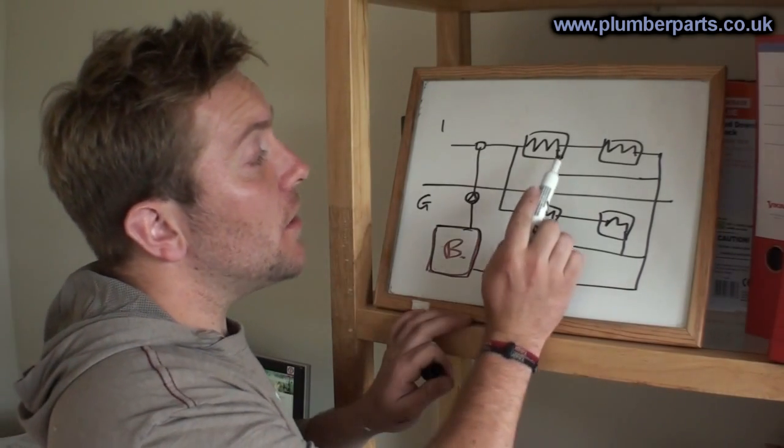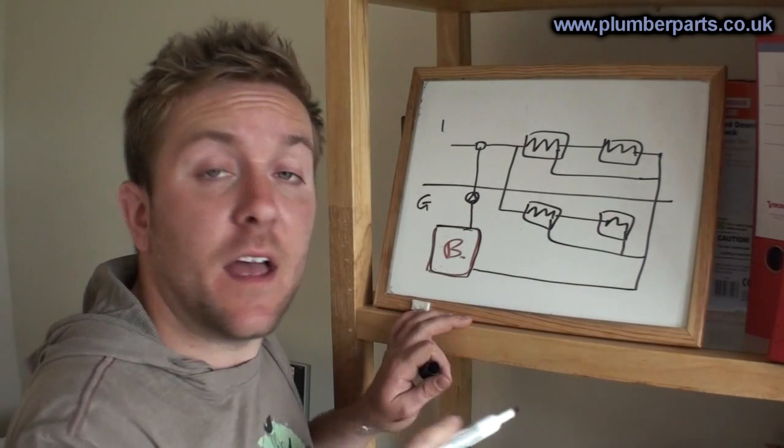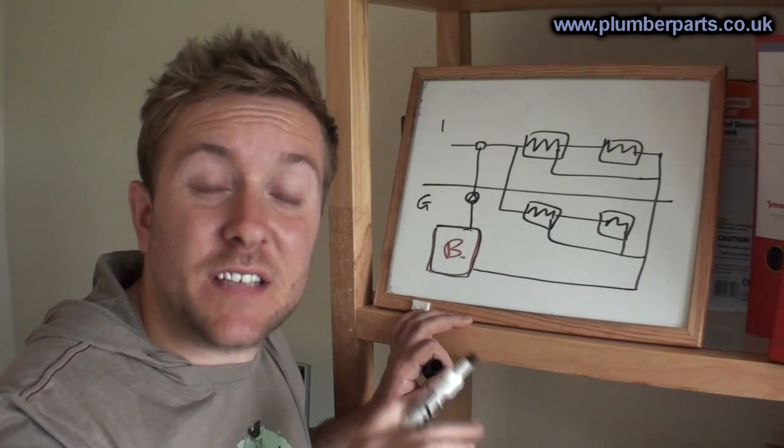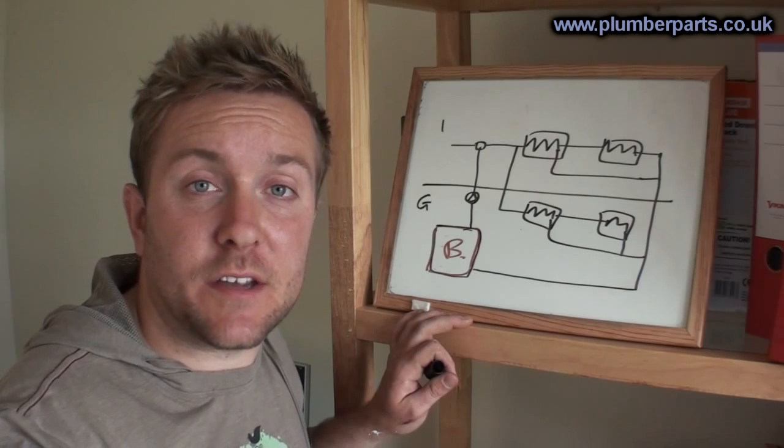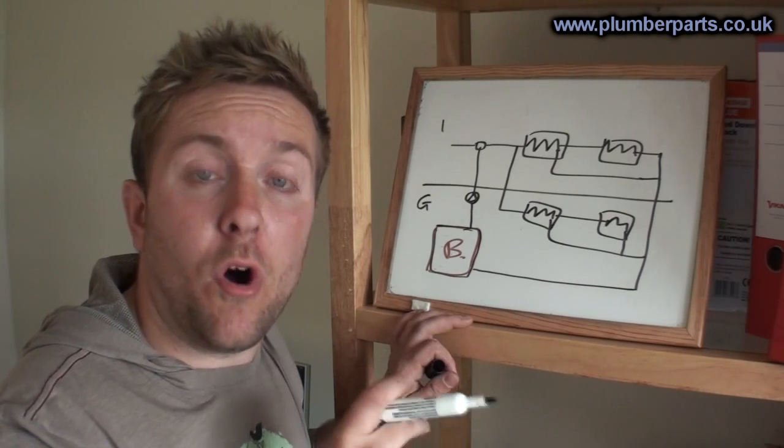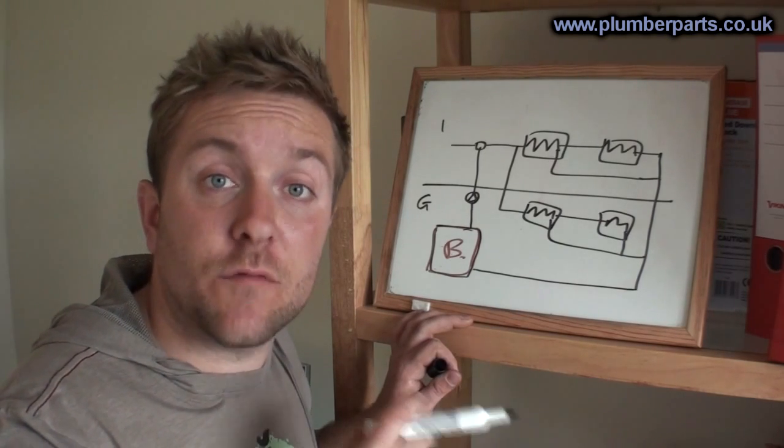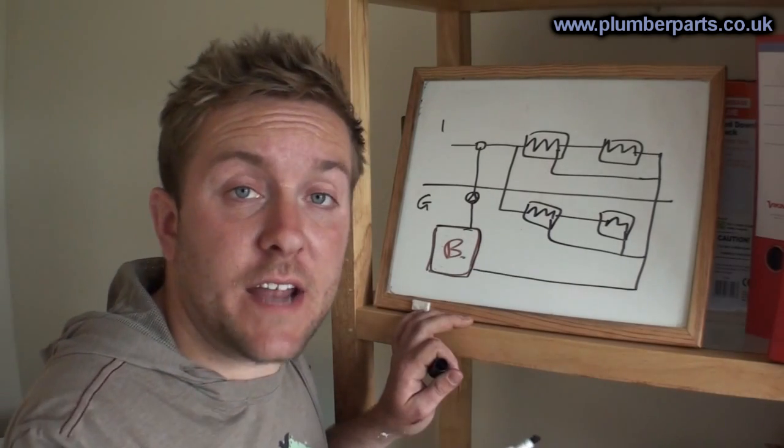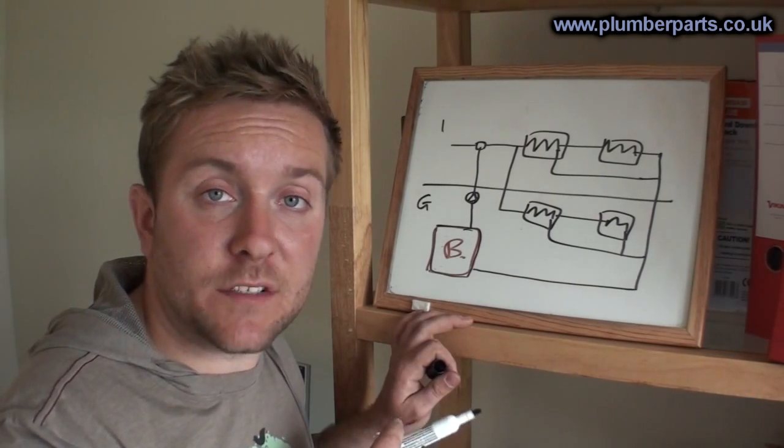So what you should do is go to the lock shield on the radiators upstairs, close them, and then open them about a quarter of a turn. You won't notice any difference in the radiators heat capacity or not, but you will notice that more hot water flow is diverted to the radiators downstairs. Now you go downstairs, make sure those radiators are open, and that means the heating system should be balanced.